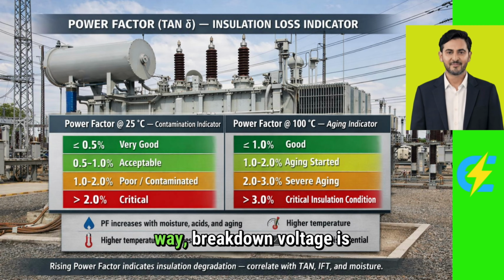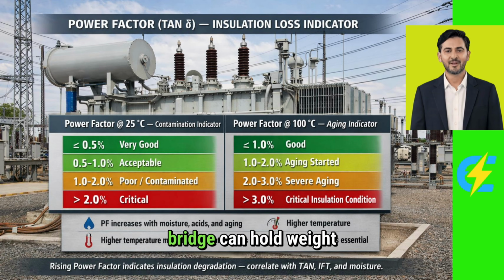Think of it this way. Breakdown voltage is like testing if a bridge can hold weight right now, but power factor tells you if the bridge materials are slowly deteriorating from the inside. So what exactly is power factor? It measures dielectric losses in transformer oil.